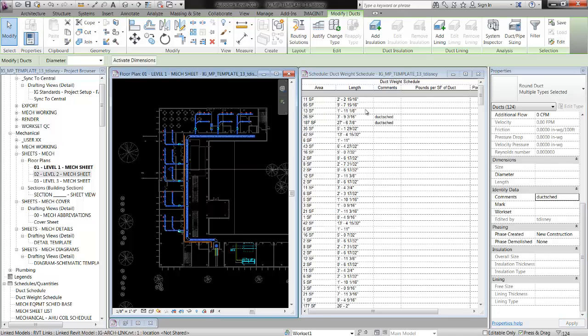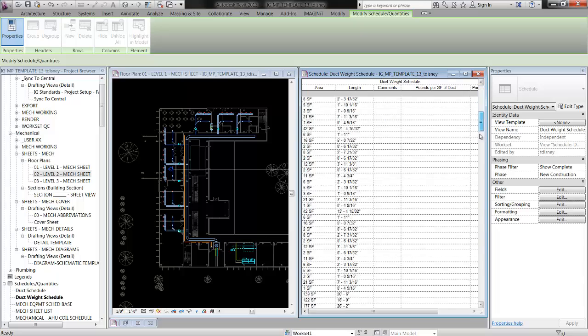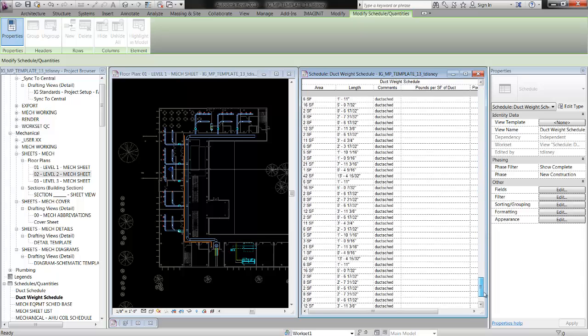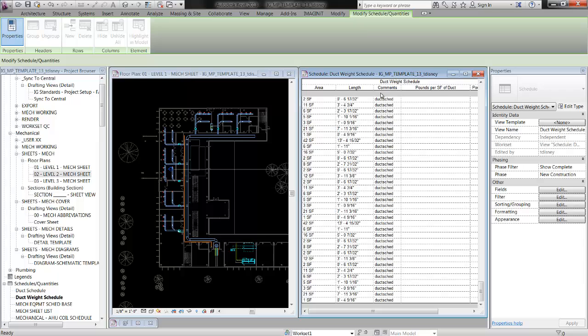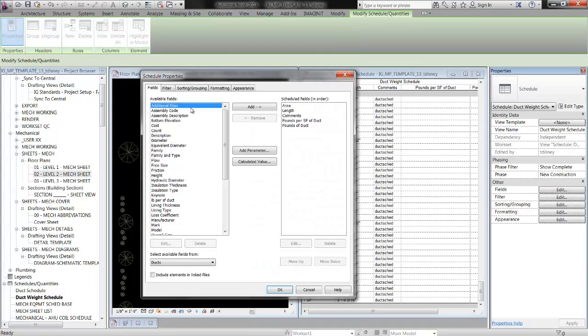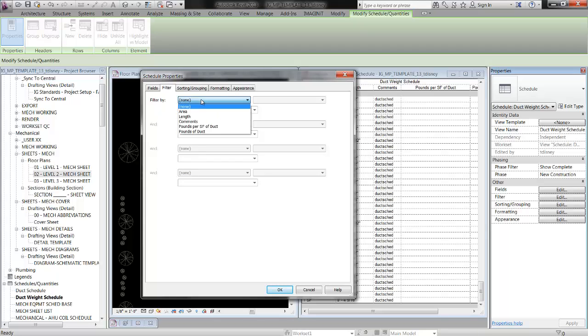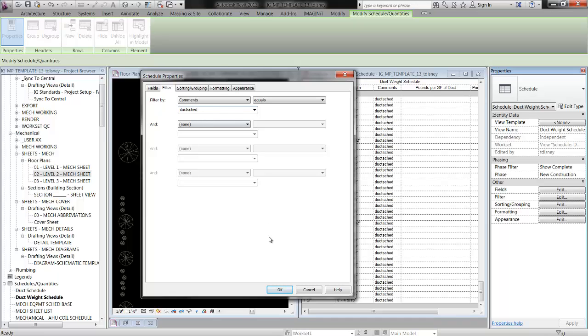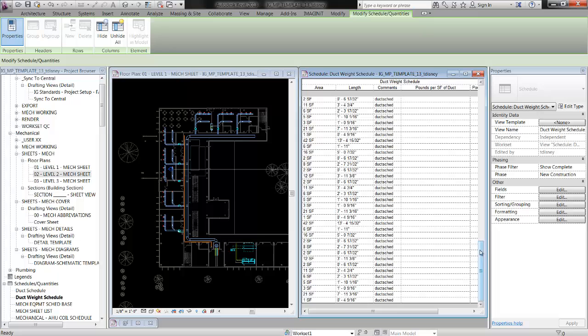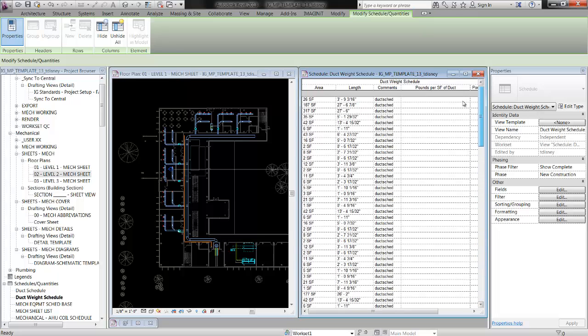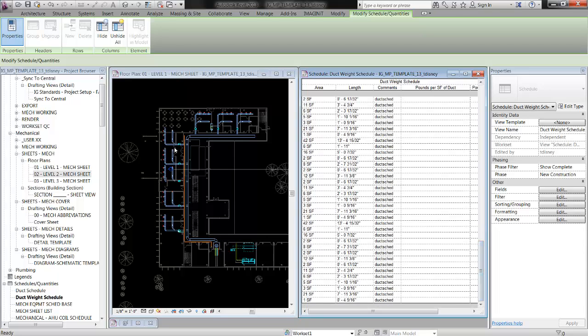Now you can see that some of these pieces of duct have this comment come up in them — those are all my level one pieces of duct work. I'm going to go back into the parameters for the schedule, hit the filter tab, and filter by comments. What I want it to do is filter by comments where the comment equals 'ductsched.' So hit OK, and now the only ducts that show up in the schedule are ones with that parameter — just these here, not ducts from the entire project.